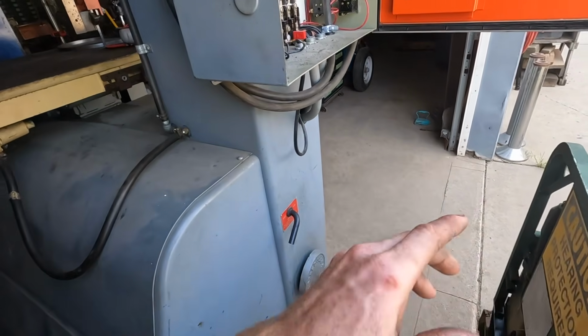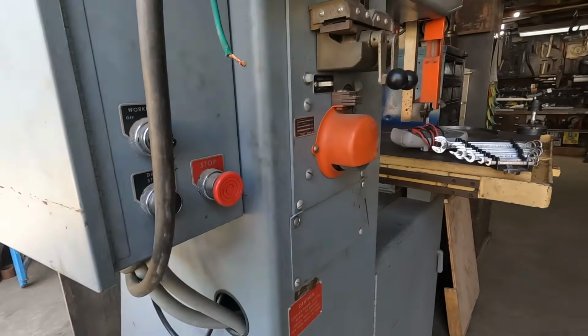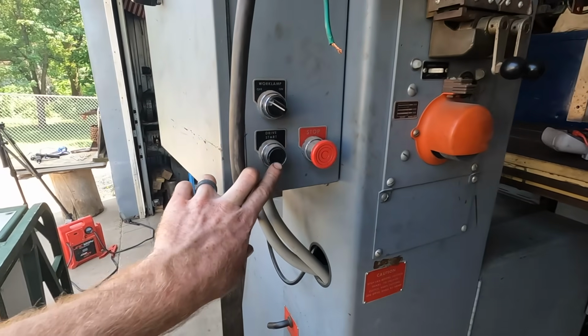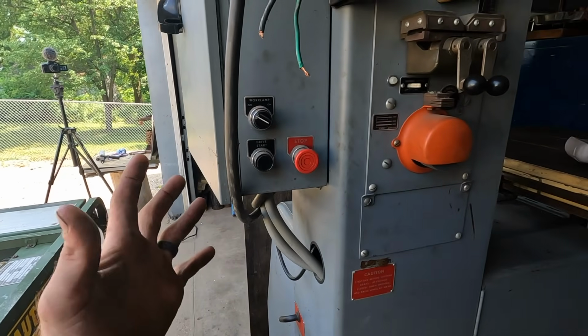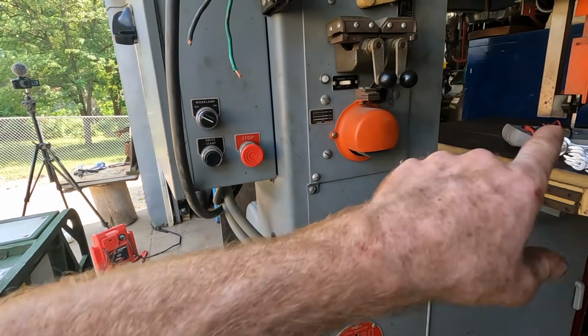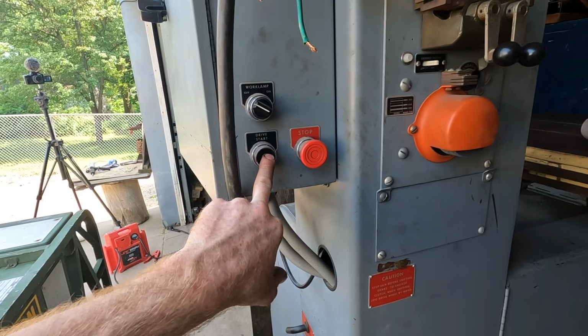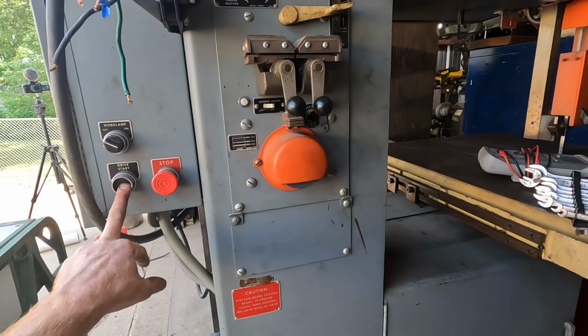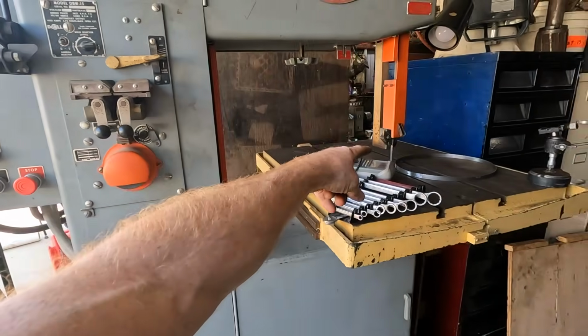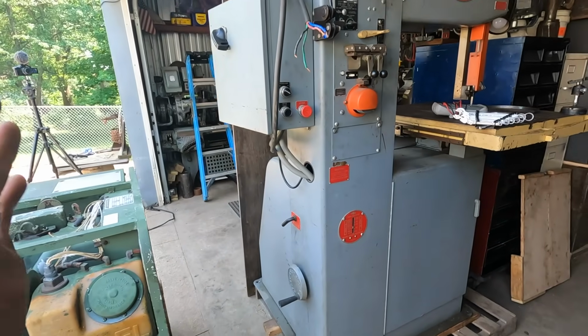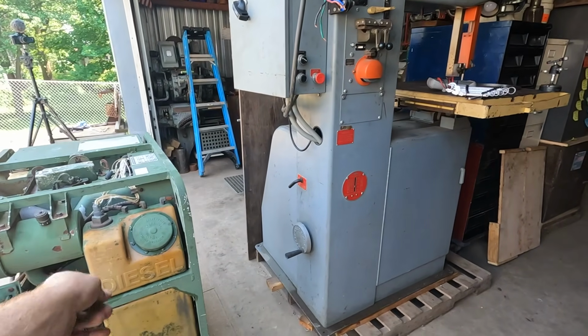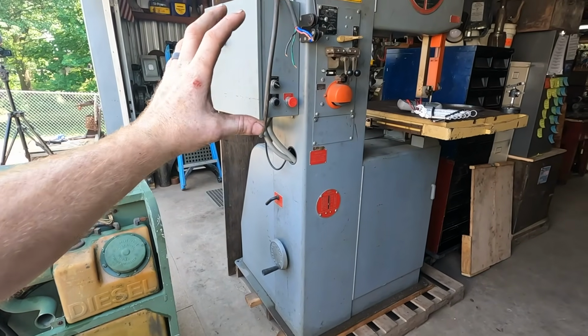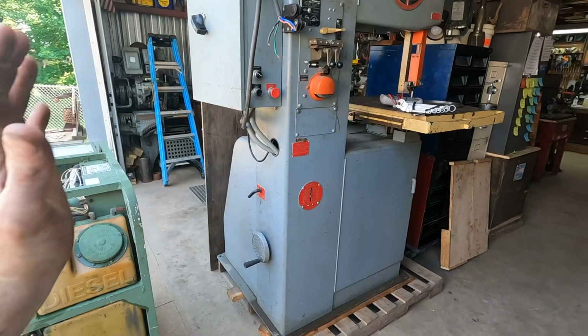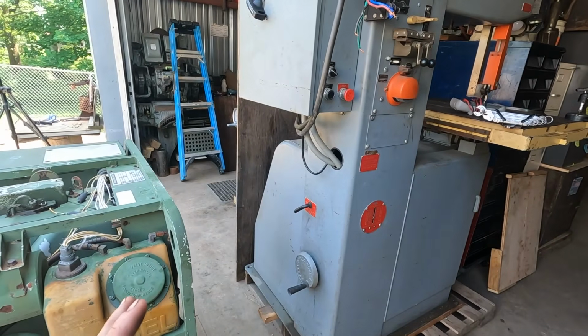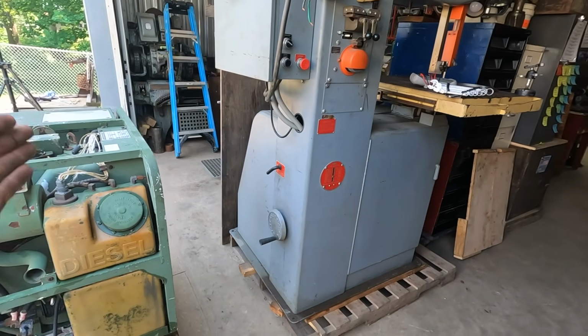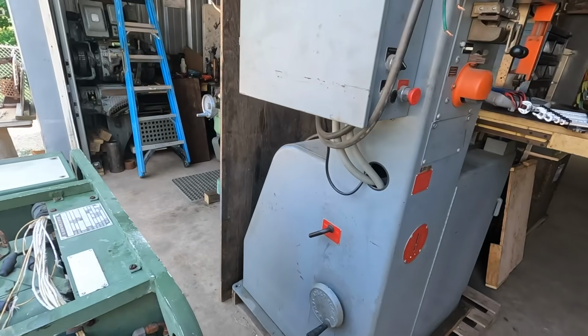So when I tried to start it, normally when I run it from the three-phase converter here in the shop, all I do is push this start drive button and it starts up. But to get it to actually run, I pushed it and held it, and after about 2-3 seconds it started up. Does that mean I'm feeding it voltage longer, letting it warm up and get fully started, and then it can run on the 208? I know that 208 on a 240 motor is not good, especially long term and especially under load. But let me know what's happening there if you know exactly.